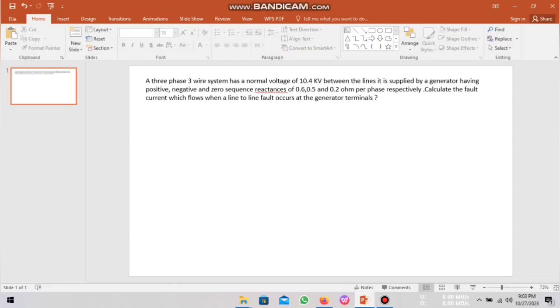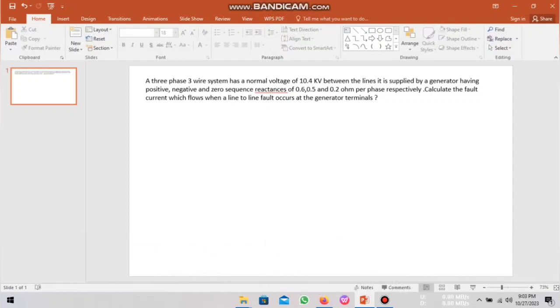Hello viewers. In today's video, I am going to talk about the topic of line-to-line fault related problem. A three-phase three-wire system has a normal voltage of 10.4 kV between the lines. It is supplied by a generator having positive, negative and zero-sequence reactances of 0.6, 0.5 and 0.2 ohm per phase respectively. Calculate the fault current which flows when a line-to-line fault occurs at the generator terminal.